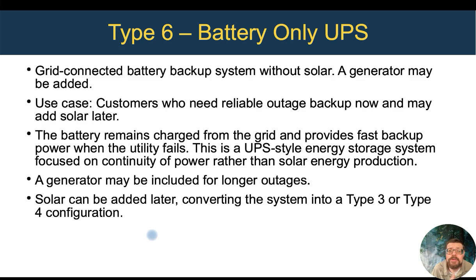And if you get the solar later and get an interconnection agreement, you could turn this into a Type 3 or Type 4 configuration depending on the utility, or it could even be turned into a Type 2 situation where it's not just doing backup power, but you're also cutting your bill down some even when the grid is there. So a lot of flexibility there, where you can start with just battery and backup power, but then go a lot of different ways in the future.